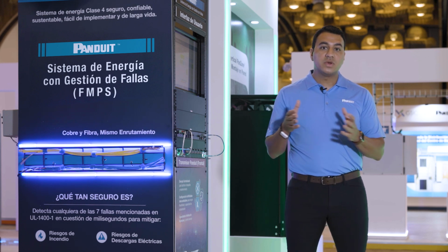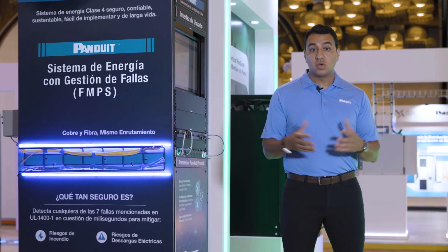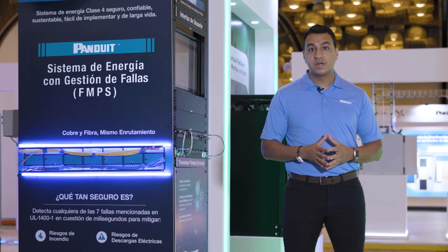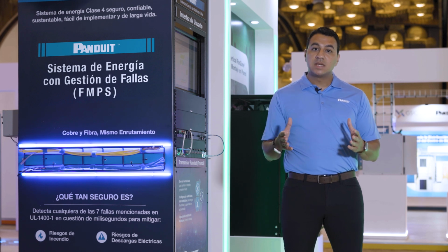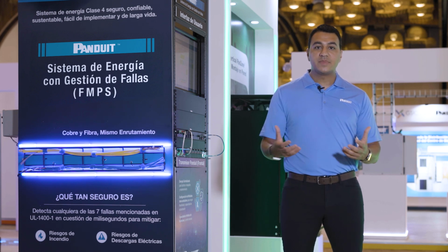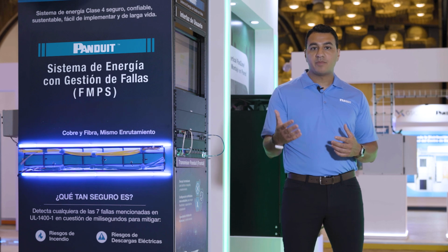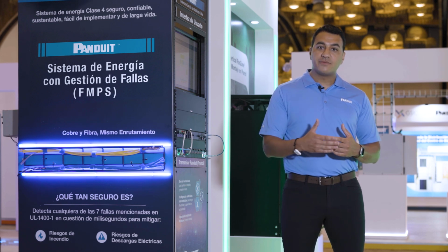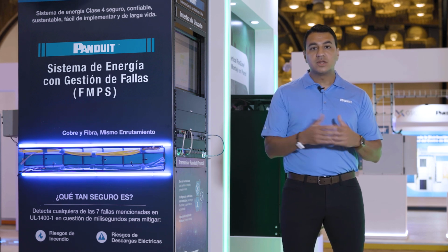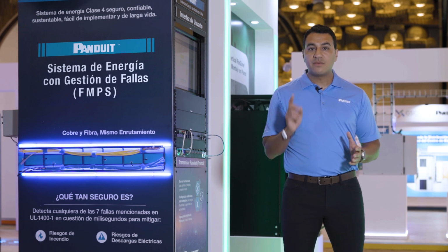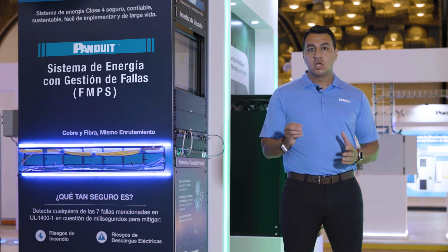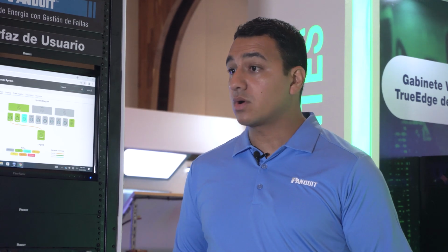But now in the US, we recently introduced Class 4. It's only been around for about a year and a half in the code now. And what it says is, now you can deploy or develop these Class 4 systems that deliver power. They can deliver 450 volts from the source. There is no limit on the power. However, you have to have a mechanism to detect faults if they were to occur.